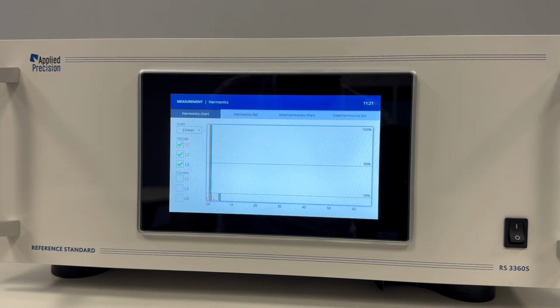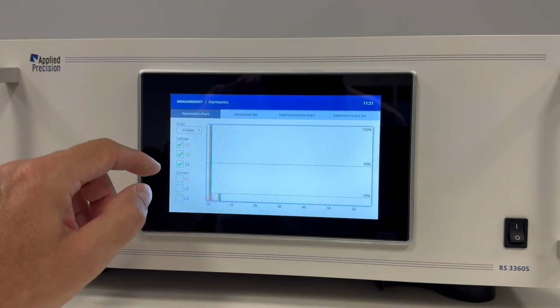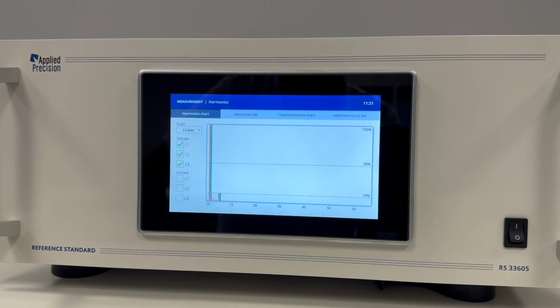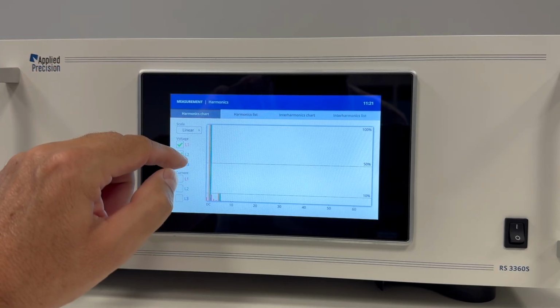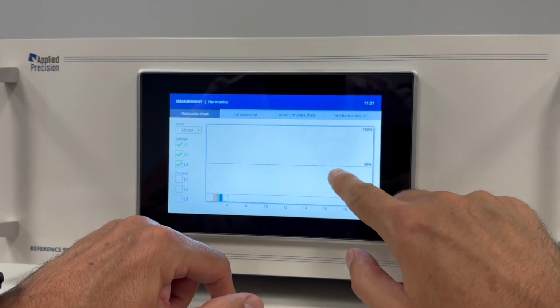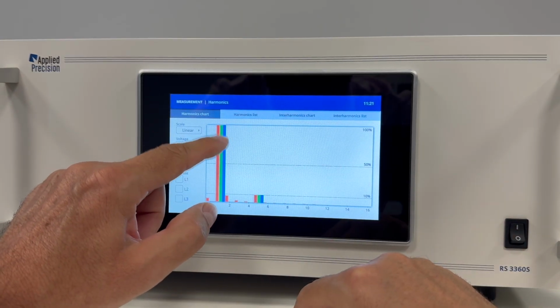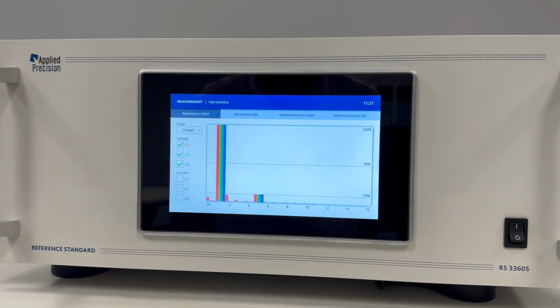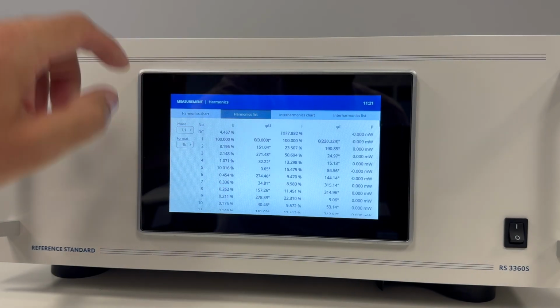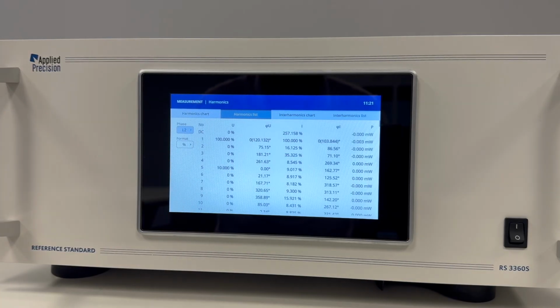So we are generating and measuring the interharmonics at the same time, and the harmonics are generated also in phases 2 and 3, but to those phases we are still applying and measuring only the fundamental and the sine wave of the fifth harmonic, to the green and blue phase. So this is what we can actually see. If we switch to L2, for example, we will be focusing only on the fifth harmonic and the fundamental. So this is about harmonics and interharmonics.